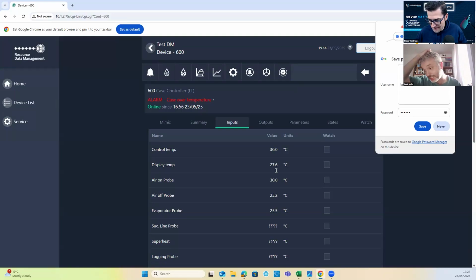And it's especially the case if you've got, let's say, a fresh meat cabinet and you want to control on that air off, but you want that -3, -4 Celsius. If they see that on the screen, they're like, why is my case so cold? Because they only want to see like 0 Celsius on that screen, right? And this is how we check the probes as well. All I would do in a cold store, I would have somebody holding that probe and I would watch what the value did. And I would then check, because I know that's the air on probe now, because I've seen the number go up.